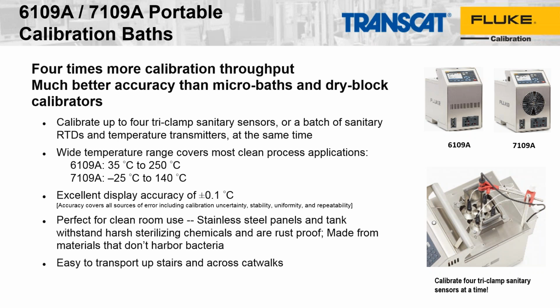And this, as with other Fluke products, takes into consideration long-term drift, stability, calibration uncertainty, and everything. So it's a comprehensive specification that covers these sources of error or sources of uncertainty. It's designed with stainless steel, so it can be used in a clean room and be easily cleaned, and with some of the chemicals that are required for cleaning clean room instruments. And because it's stainless steel, it won't harbor bacteria, which was a big deal for the customers that we worked with on developing this. So it's portable. You can see the handle there on top, a nice strong handle, so you can take it into facilities where you need something that's portable.